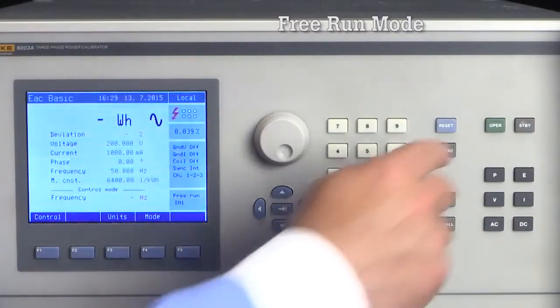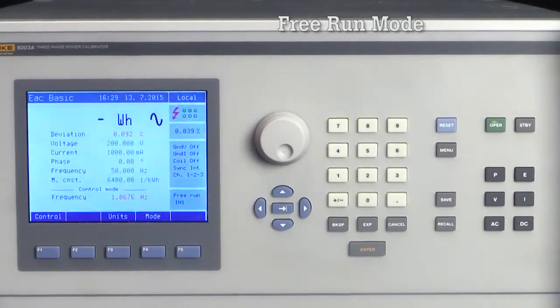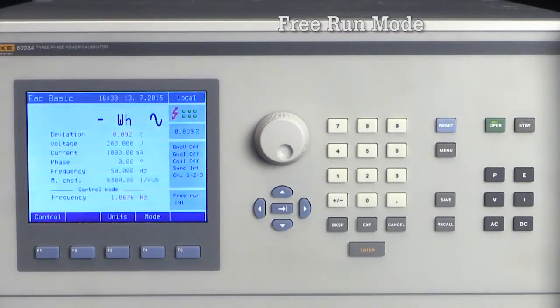To start the test, I will push operate and the test starts. The 6003A outputs 200 volts 1 amp into the UUT. In other words, it delivers 200 watts to the meter. The 6003A receives the pulses back from the meter and, based on the meter constant, expects an exact frequency of the pulses. The 6003A continuously shows the deviation between the measured frequency and expected frequency as a percentage.